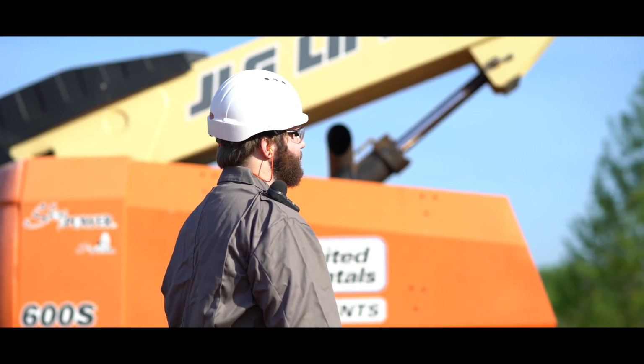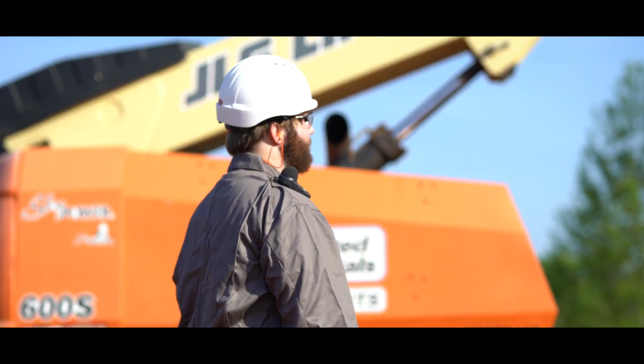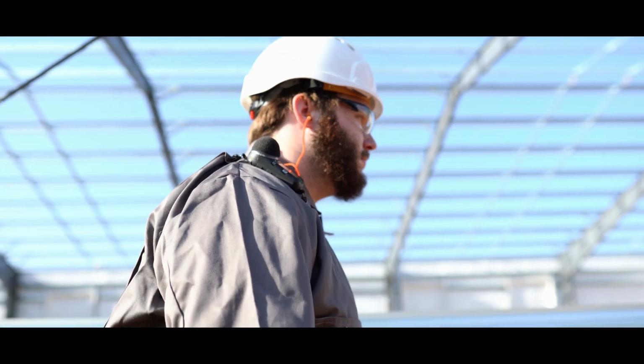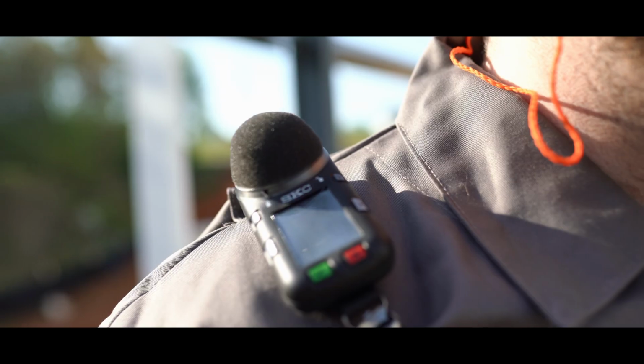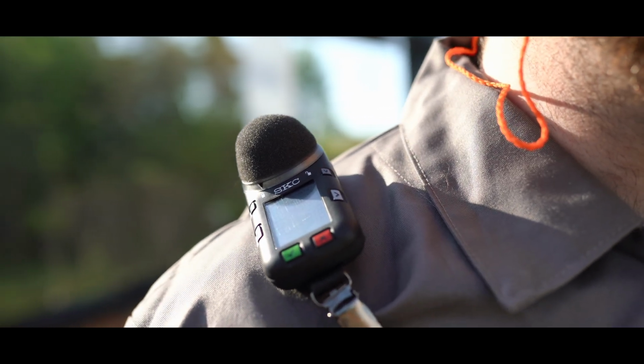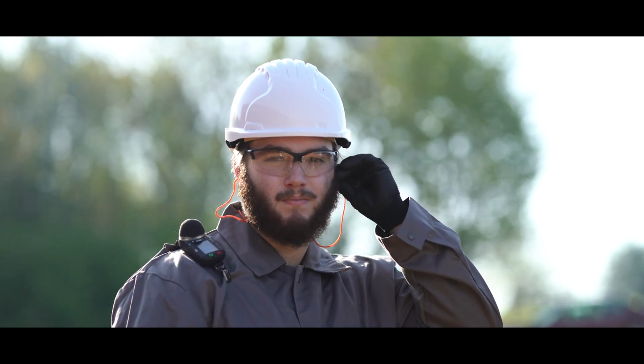Calibration is a very important part of any industrial hygiene instrument, but specifically in the noise arena where they have to calibrate before and after use. And that's always been a problem in the noise survey—having to find a menu system and go in to make sure they're calibrating it properly.